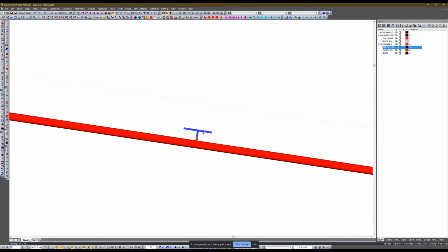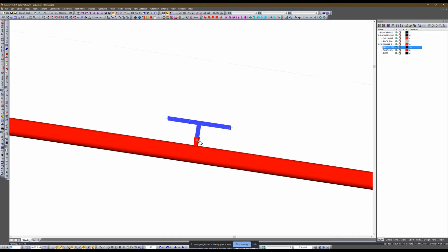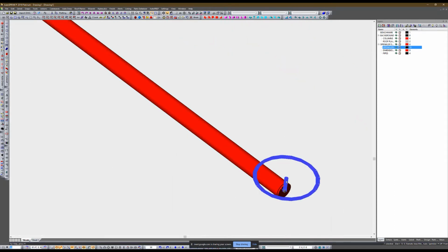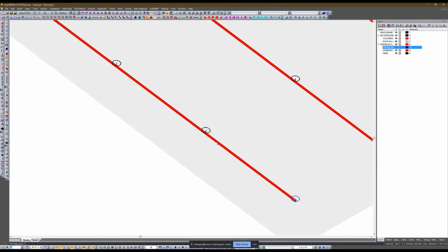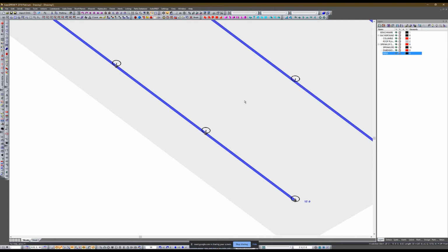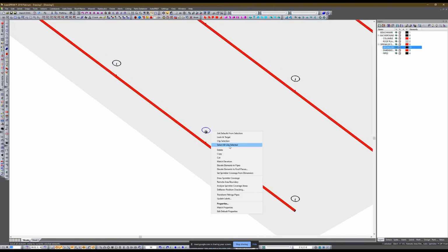So in a situation like this, if I wanted this sprinkler connection point to be down at this 1 foot location, there is an option here. So you can see the end point here, it left everything where it was because the pipe didn't extend beyond, so the program couldn't place an outlet there. So what we could do at this point is select all of these things, just manually lower them, reselect all of the sprinklers, re-elevate them to the roof plane. You can see these change position.